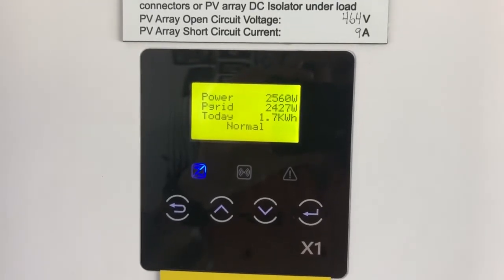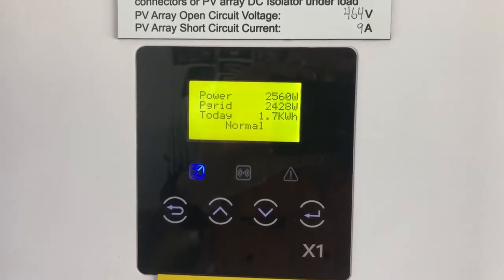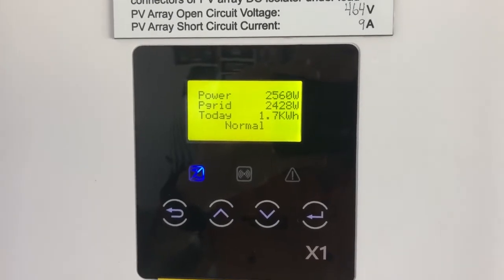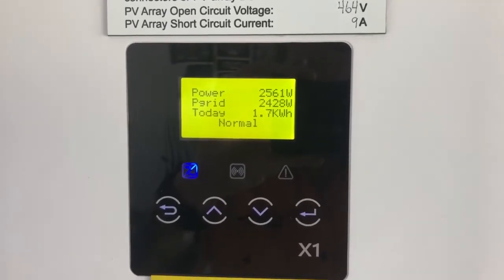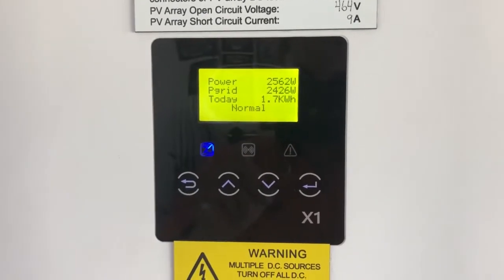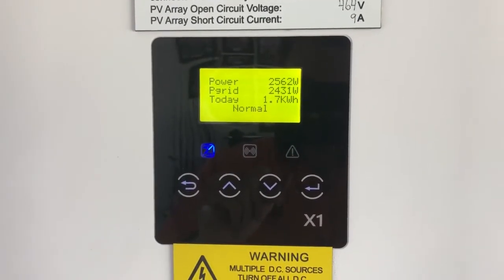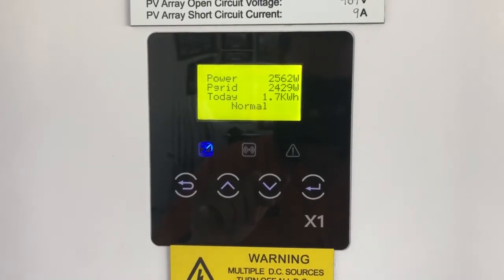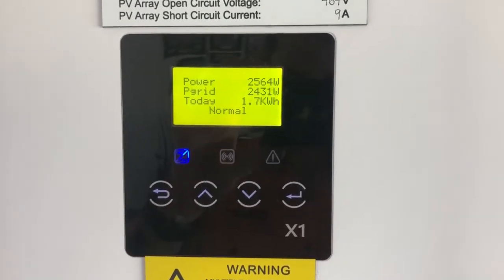You can see here it shows P grid — that's the power going back to the grid. We've got power coming in from the solar at 2560 watts and power going back to the grid at 2430 watts. This inverter has a meter connected so it can monitor export and consumption from the grid as well.